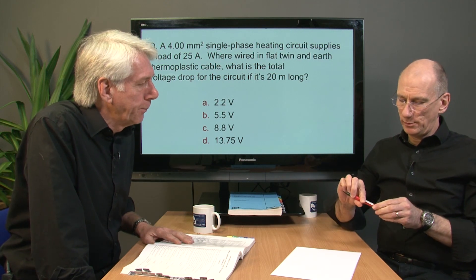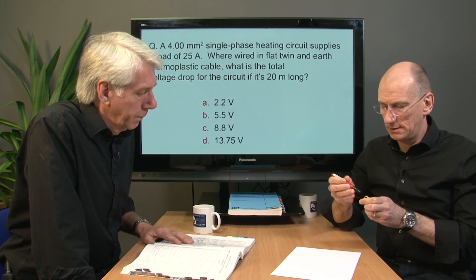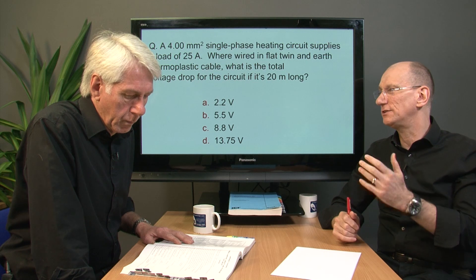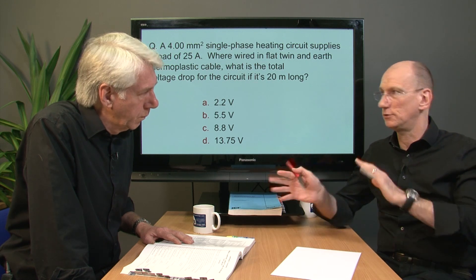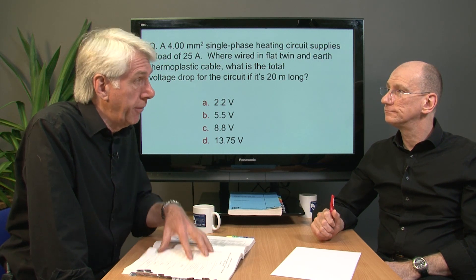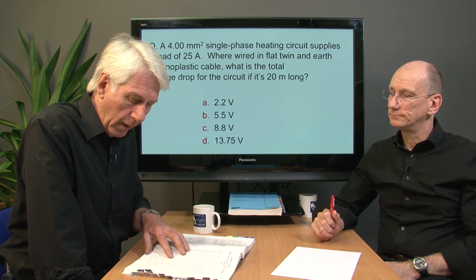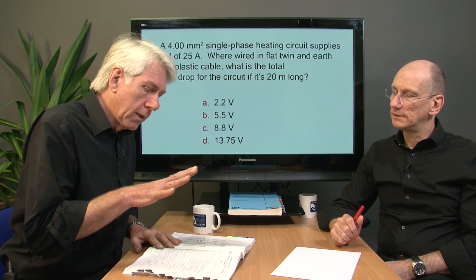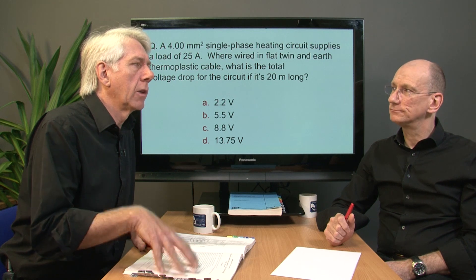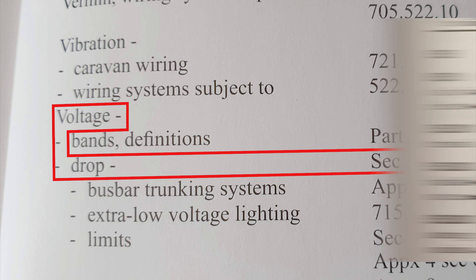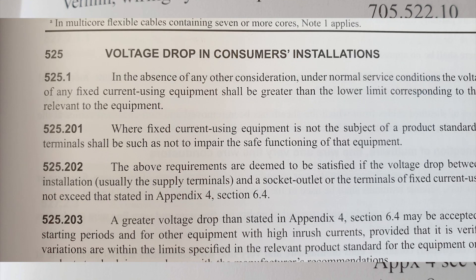So where do we find that? Well we need to look in the back of the book. It contains an appendix that covers all cables for current carrying capacity and voltage drop. It covers single phase cables, three phase cables, armoured, single, and that is in Appendix 4. Appendix 4 is a very useful appendix to become familiar with. If you're working with your book have a look at it now. The default position is to go to the index, which will direct you to section 525, which covers voltage drop, which mainly directs you back to Appendix 4, section 6.